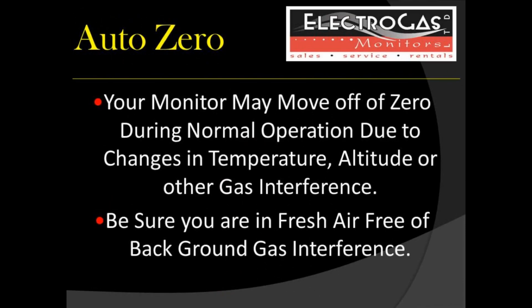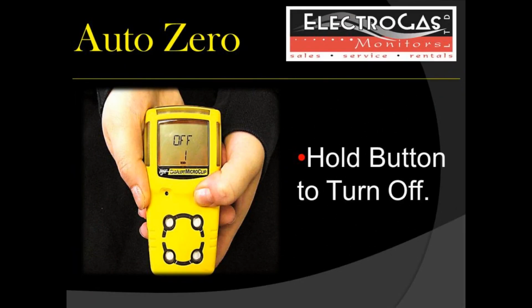During normal operation of your monitor, the sensor reading may fluctuate off of 0 even when no gas is present. This can be caused by changes in temperature, altitude, or the presence of other gases in the air. If this occurs, you can perform an auto zero to reset the sensors. To begin the auto zero process, ensure you are in a fresh air environment free of any background gas interference. Push and hold the blue button as if you were turning your monitor off.